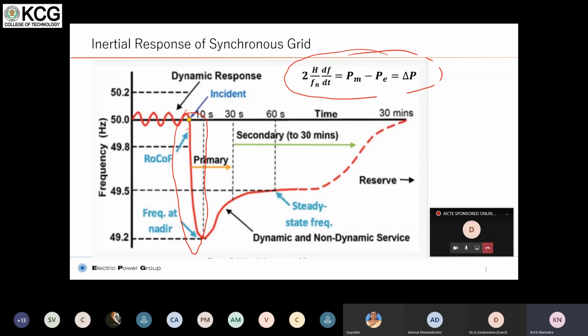Essentially, today's topic covers the time frame from when a disturbance happens in your system to less than 10 seconds, where none of the actions such as the governors or the primary, secondary, or tertiary frequency control come into the picture. Also, we will discuss ambient data, where the frequency never remains constant because of small changes in load and generation imbalance. Whenever that happens, your dynamic equation always comes into the picture.